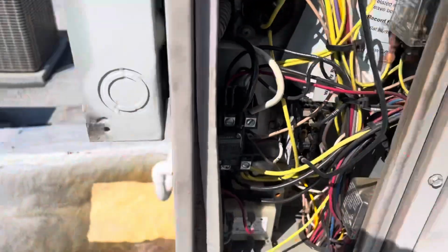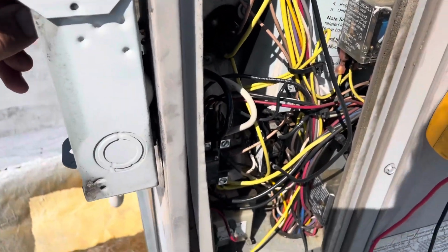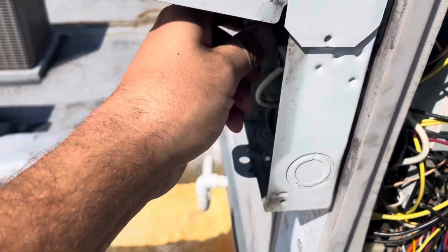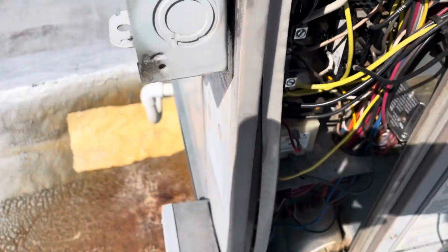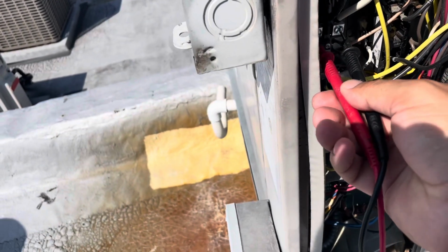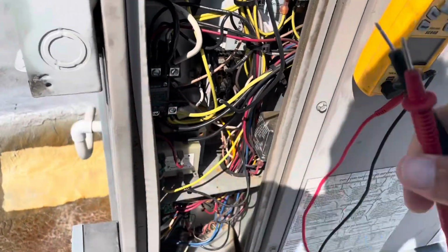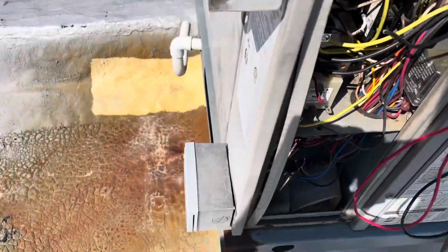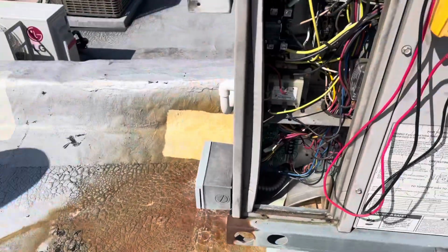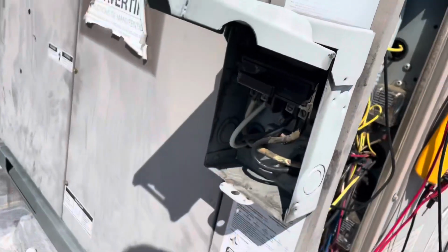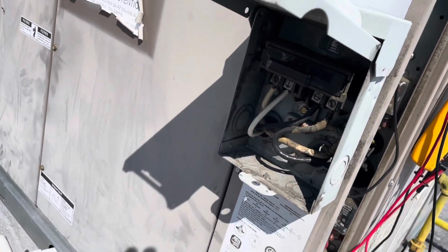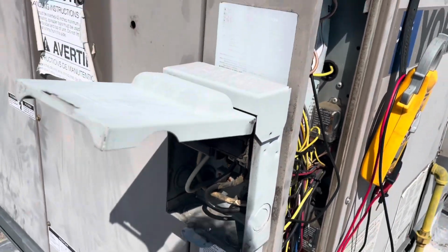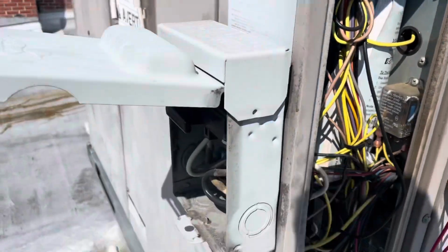We got voltage now, and I'm shaking it trying to get it to malfunction, and it's not. So somebody probably didn't plug it back in properly last time, but we're still going to recommend replacing the disconnect. It is worn out, had a little bit of charring on it, so we'll get him a new disconnect.